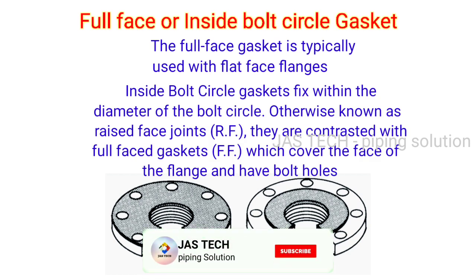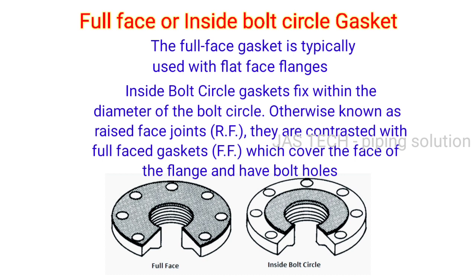Full face or inside bolt circle gasket: The full face gasket is typically used with flat face flanges. The inside bolt circle gasket is fixed within the diameter of the bolt circle, otherwise known as a raised face joint. They are contrasted with full face gaskets, which cover the full face of the flange and have bolt holes.